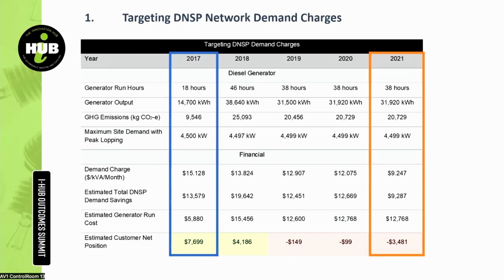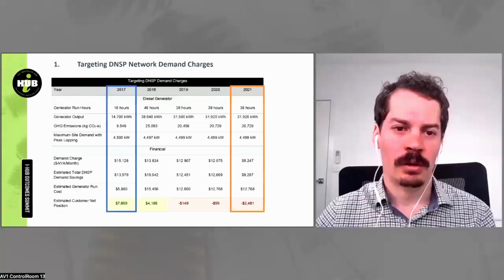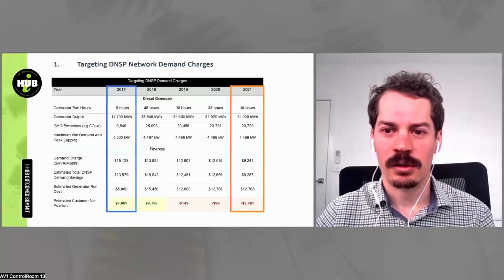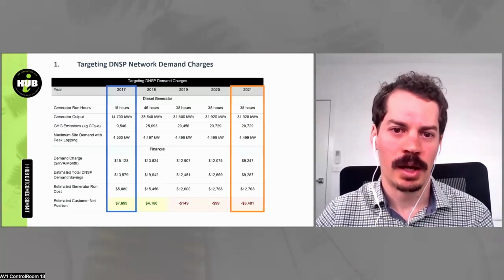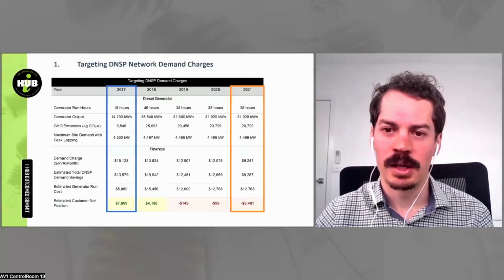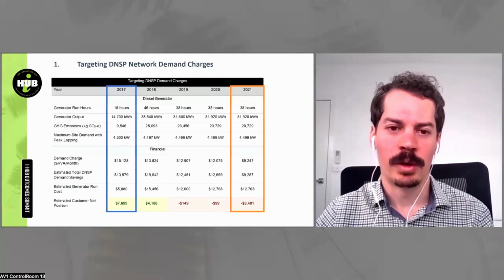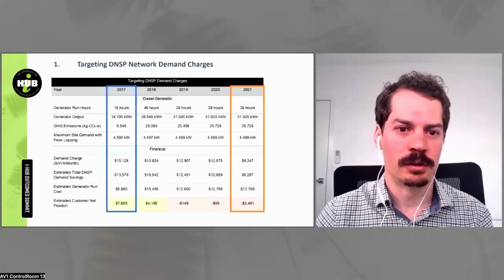On the other hand, 2021 was the worst year, which is highlighted in orange there. And during this year, the network demand charges had significantly fallen from the 2017 rates, which caused less savings and an overall negative customer position. And the results of this type of participation shows how a positive position can quickly change to a negative position without some kind of revised strategy on that maximum demand limit. So one of the main issues with targeting these demand charges is not underloading the generators. So you often have to run them at higher outputs than the demand reduction you actually need. So this type of demand response can work a lot better with smaller generators rather than larger generators.